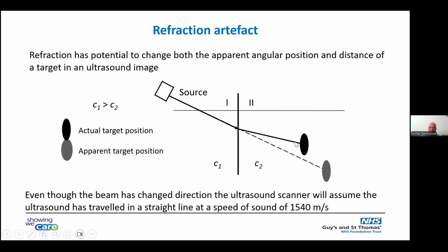The beam is being refracted, it hits the actual target, the black dot, then it gets returned to the transducer. But the scanner thinks that the target is coming from the direction at which it sent out the beam. So it thinks it has been received along the dotted line, and it's positioning the target at the distance corresponding to that time delay, but along the line that it sent out the beam. So the apparent target position is going to be incorrectly represented due to refraction.